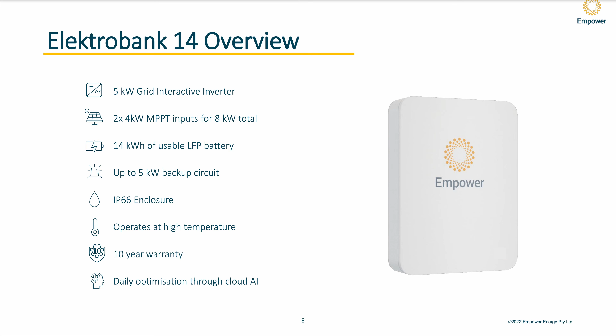Yeah. Okay. Cool. We've talked a bit about the IP66 enclosure, but that's really key for Australia, especially all along the east coast. You've got so many houses next to the sea. It's crazy. Now, you've got there operates at high temperature. Can you be more specific? Yeah, so the lithium iron phosphate cells operate up to 55 degrees C, so that's the actual cell temperature. So temperature gets tricky to talk about with battery systems, because there's a lot of thermal mass inside the battery. So people ask, how hot can the battery run in terms of what's the ambient temperature? It's a very hard question to answer, because it really depends on the load profile. So how fast is the battery charging and discharging? What's the solar doing?